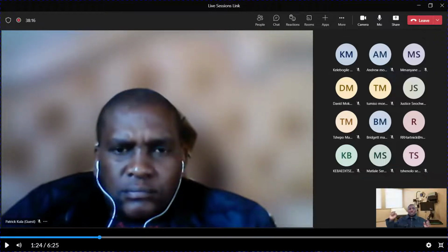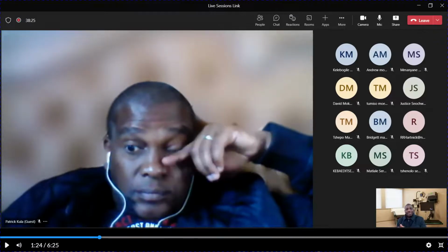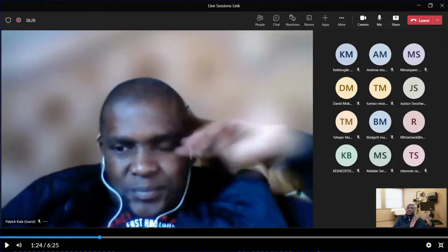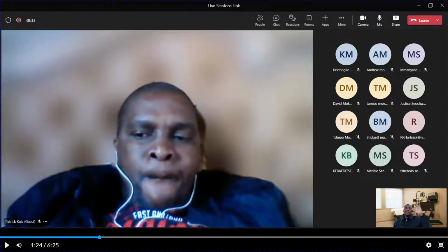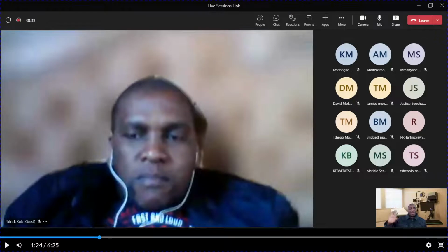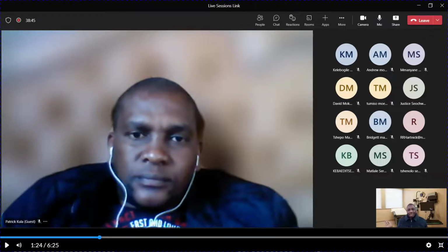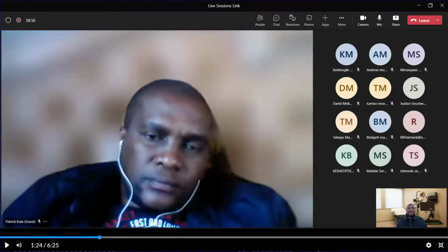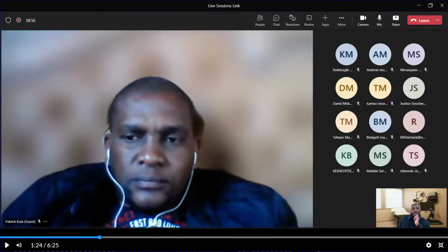So by combining the two, the first one and the second one, you can now tell, okay, this equipment allows this much entry of solid objects and this much entry of water. Where you have an X, let's say you have X8, for instance. X means that the aspect of dust and solid objects is not stated, is not important, therefore it's not stated. 8 means it is waterproof beyond 1 meter, and that's the highest level of protection against the entry of water.